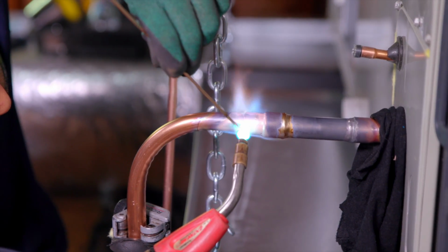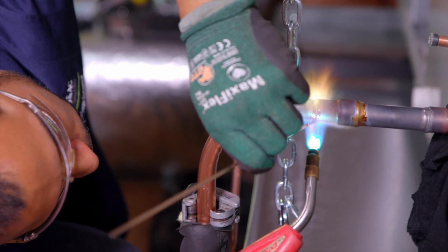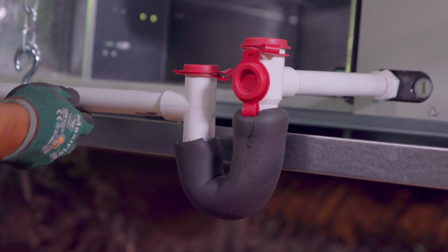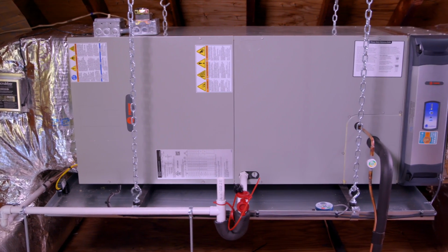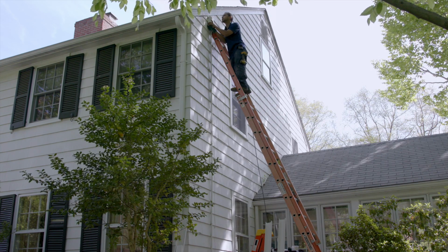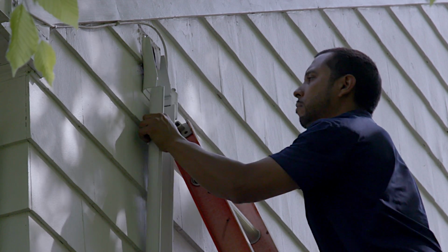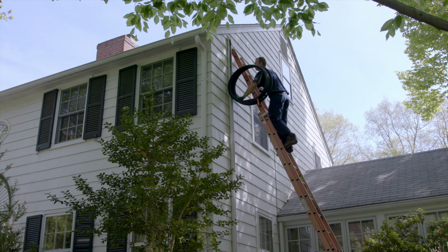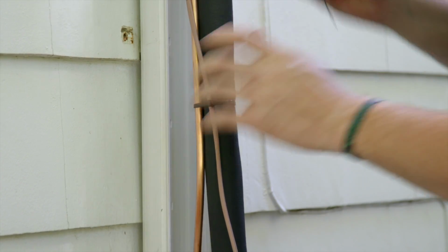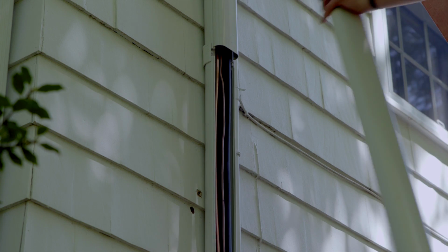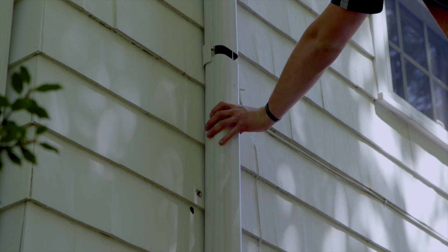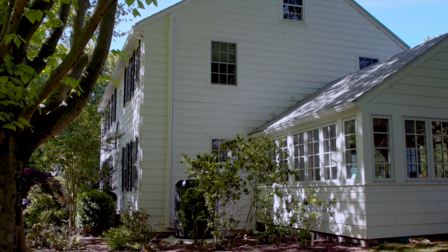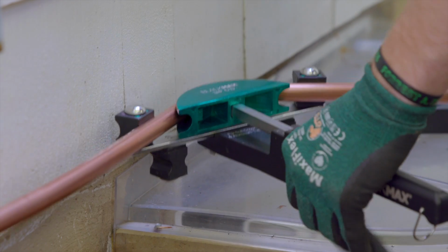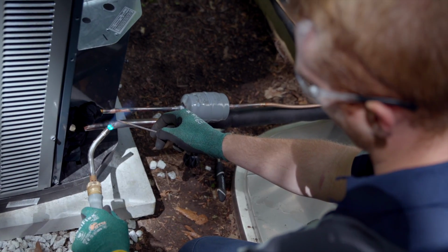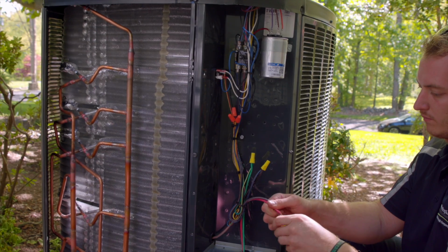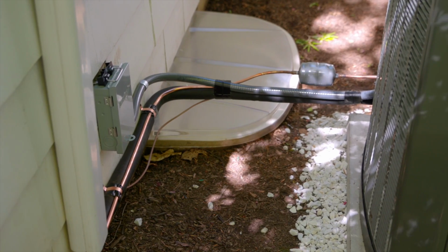The next step in this installation is to solder the refrigerant lines in place and connect the condensate drain line and P-trap. This pretty much finishes things up here in the attic. Outside, it's time to install the line set enclosure, starting at the top and working to the bottom. The refrigerant lines are uncoiled, strapped together, and set into the enclosure, and the cover snapped into place. Quite a difference from the old look to the new. Next, the refrigerant lines are bent into shape and soldered in place. Brian then makes the final electrical connections, and the condenser is ready to go.